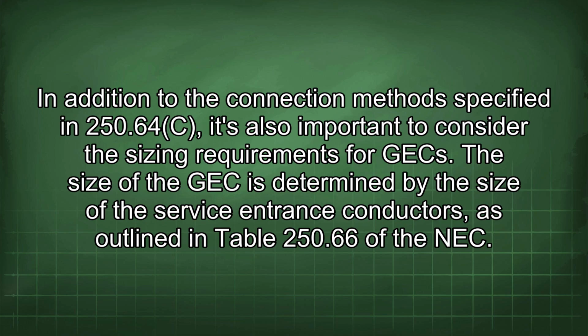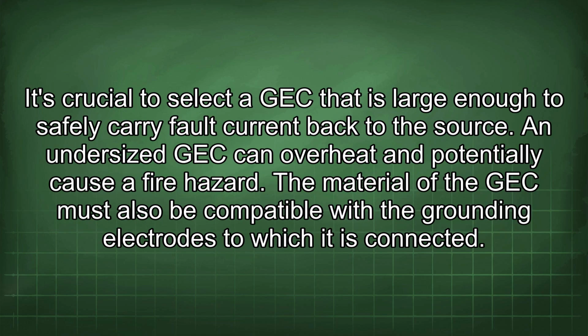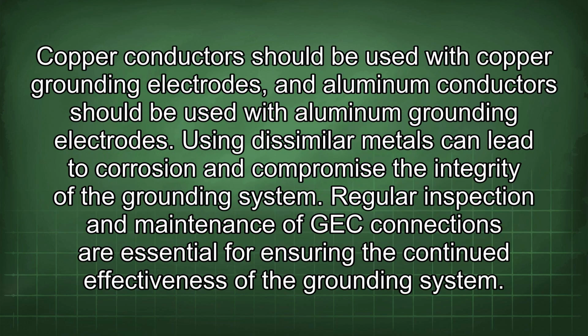of the NEC. It's crucial to select a GEC that is large enough to safely carry fault current back to the source. An undersized GEC can overheat and potentially cause a fire hazard. The material of the GEC must also be compatible with the grounding electrodes to which it is connected. Copper conductors should be used with copper grounding electrodes, and aluminum conductors should be used with aluminum grounding electrodes. Using dissimilar metals can lead to corrosion and compromise the integrity of the grounding system.